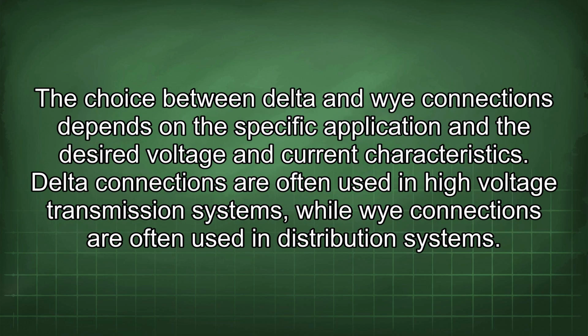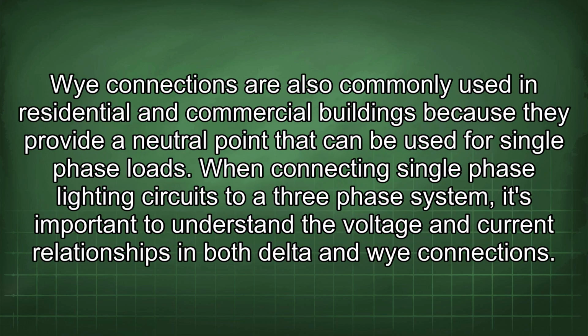The choice between delta and Y connections depends on the specific application and the desired voltage and current characteristics. Delta connections are often used in high-voltage transmission systems, while Y connections are often used in distribution systems. Y connections are also commonly used in residential and commercial buildings because they provide a neutral point that can be used for single-phase loads. When connecting single-phase lighting circuits to a 3-phase system, it's important to understand the voltage and current relationships in both delta and Y connections.